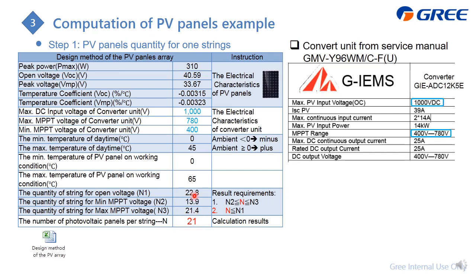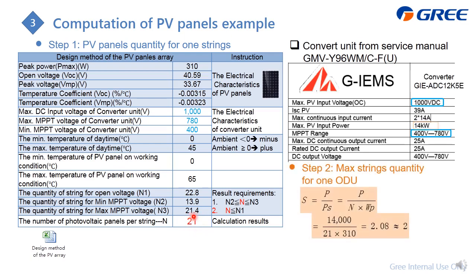If this is correct, you can get one string with 21 pieces of PV panels. For how many strings, you get P from here as 14 kilowatts, so finally we can get a max of 2 strings.